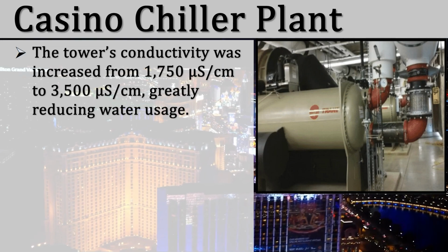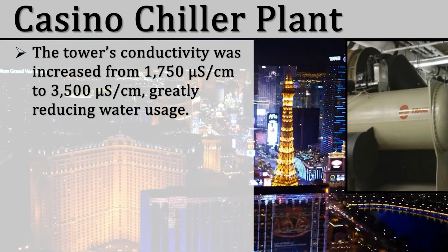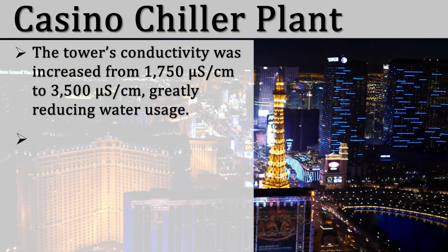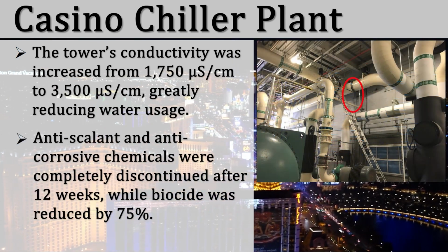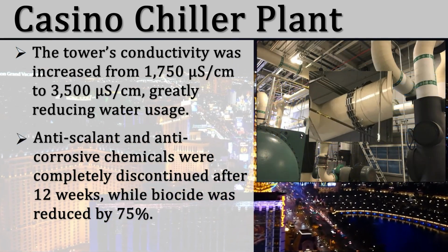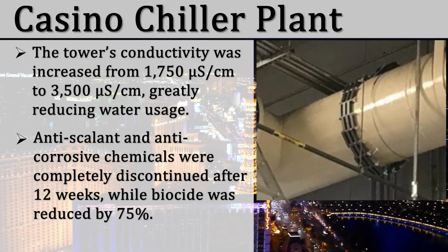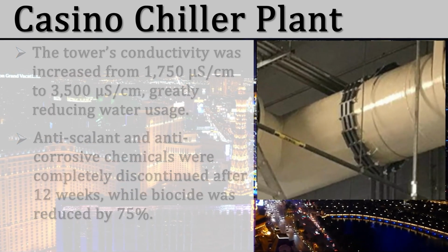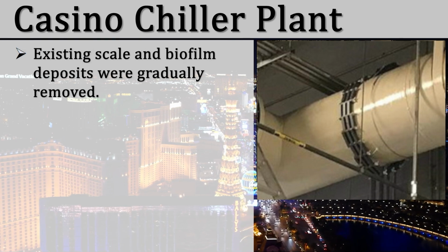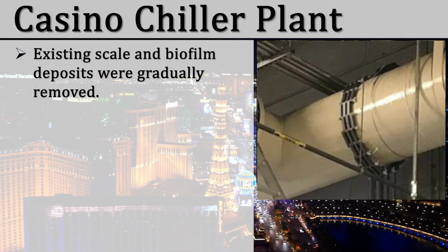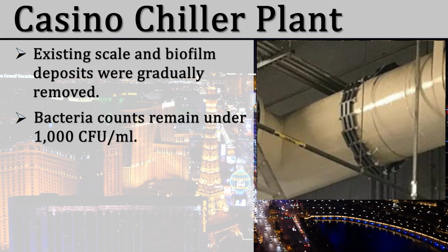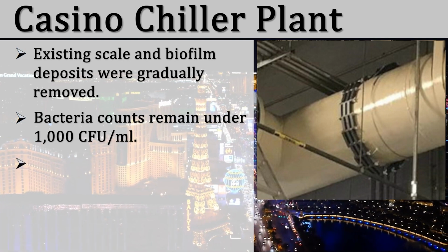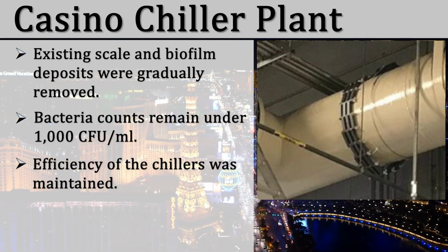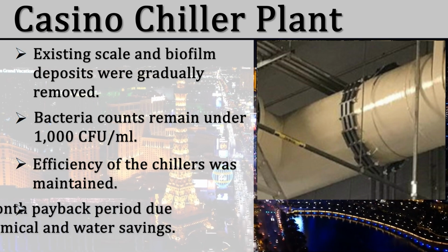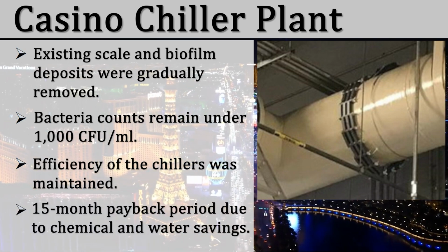Results: the tower's conductivity was increased from 1750 microsiemens to 3500 microsiemens, greatly reducing water usage. Anti-scalant and anti-corrosive chemicals were completely discontinued after 12 weeks, while biocide was reduced by 75%. Existing scale and biofilm deposits were gradually removed. Bacteria counts remain under 1,000 CFU per milliliter. Efficiency of the chillers was maintained. 15-month payback period due to chemical and water savings.